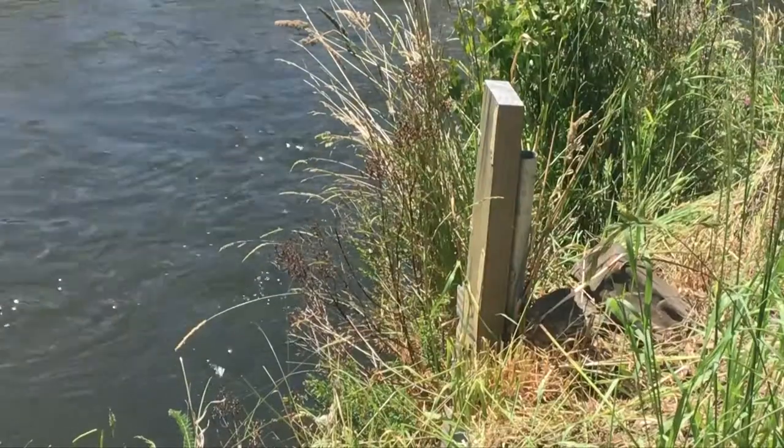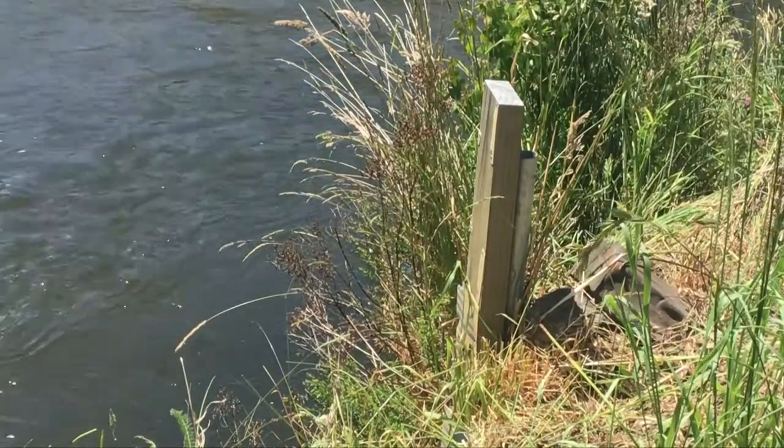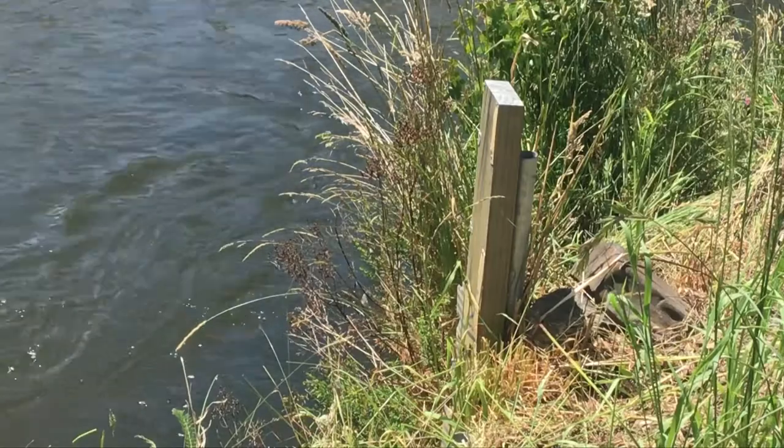Following flood and high water events, the officers try to visit all sites in the network as soon as possible. All flow sites and water level sites have to be visited at least monthly. If there's been an event like there has been just recently, we try to visit them pretty soon after to see if there's any damage, debris caught around them, or if it's reading accurately.